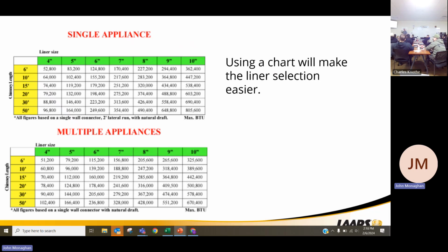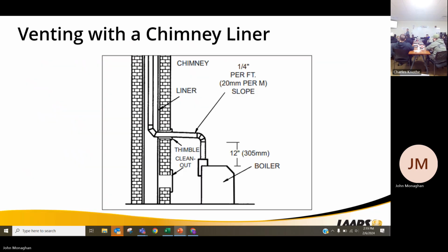size chimney you need. But lining it, it's not lining it, it's resizing it, because oftentimes it was for that 60%, 70% product where we had super high flue gas temps. But a JX and any other 84% product normally needs to be lined. Going through your chimney liner, dropping your liner down through your thimble, pulling everything out. Most of the time, the clean out down the bottom would no longer be used. You need to install a clean out on there if it's required.